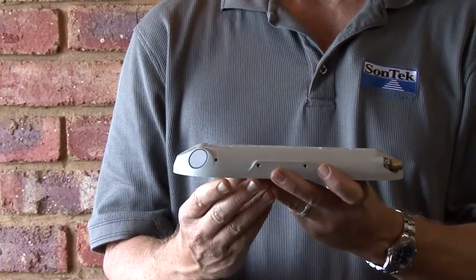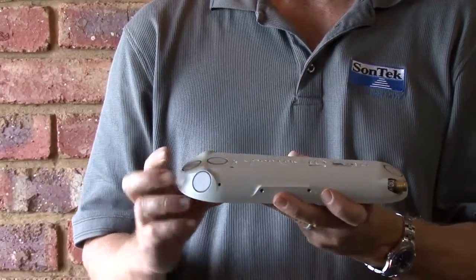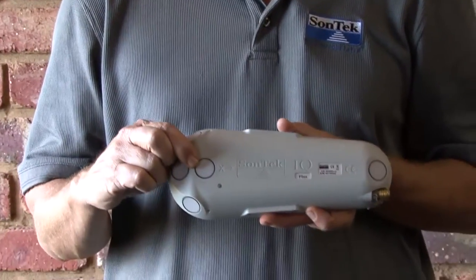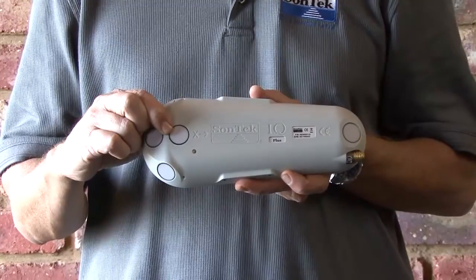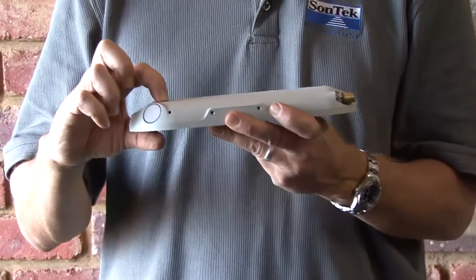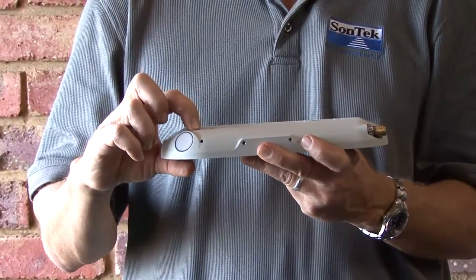The next measurement that we need is actually the water level, and so we make the water level measurement using this 3 megahertz acoustic vertical beam, and we also have a pressure sensor that's embedded inside the housing as a redundant measurement.